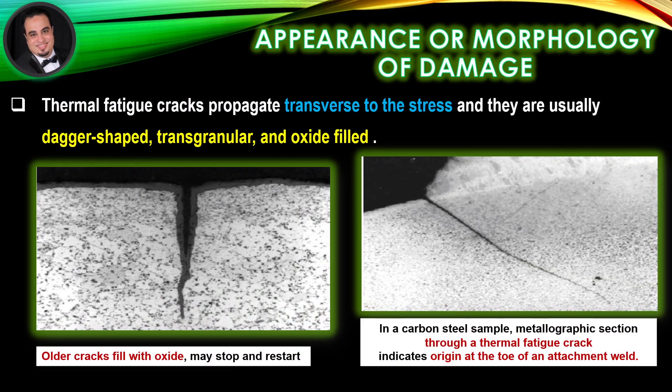Appearance or morphology of damage: thermal fatigue cracks propagate transverse to the stress, and they are usually dagger-shaped, transgranular, and oxide-filled. As illustrated in figures of a carbon steel sample, a metallographic section through a thermal fatigue crack indicates origin at the toe of an attachment weld. Older cracks filled with oxide may stop and restart.